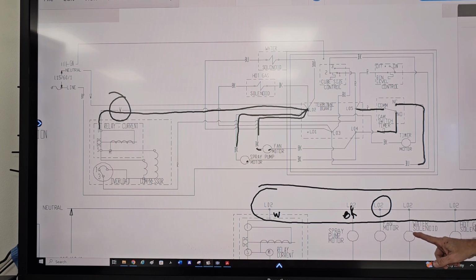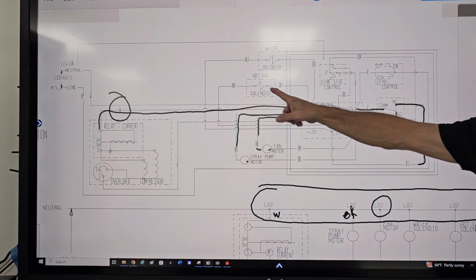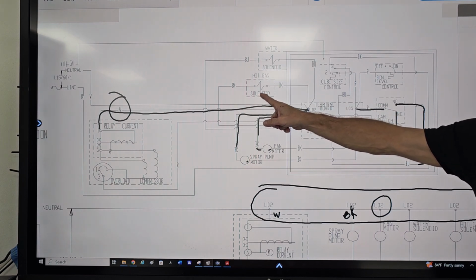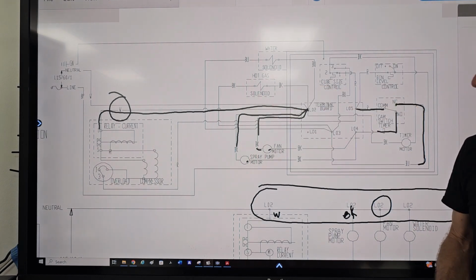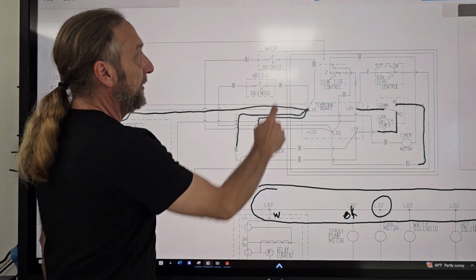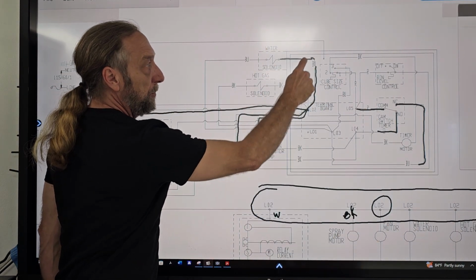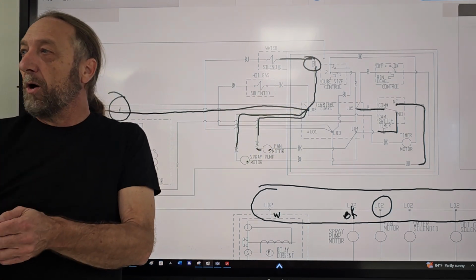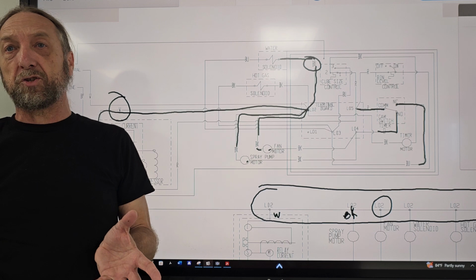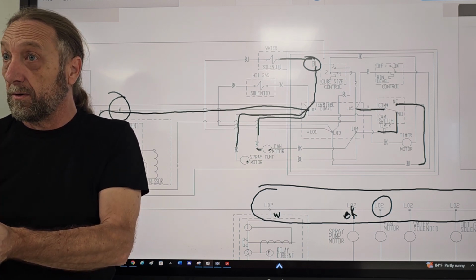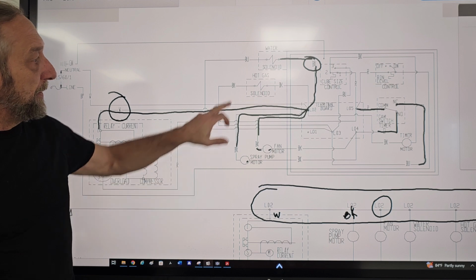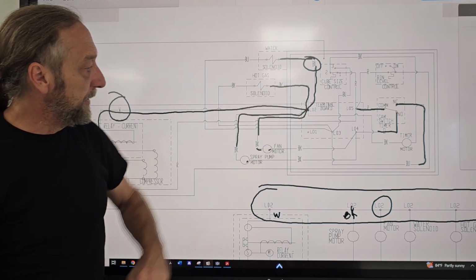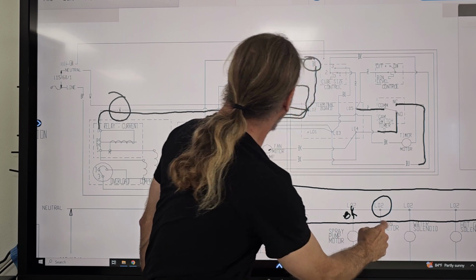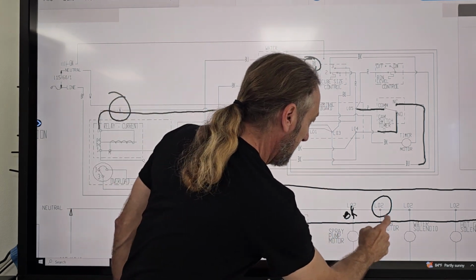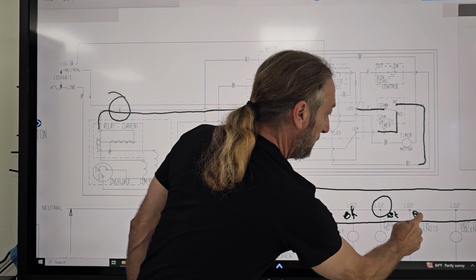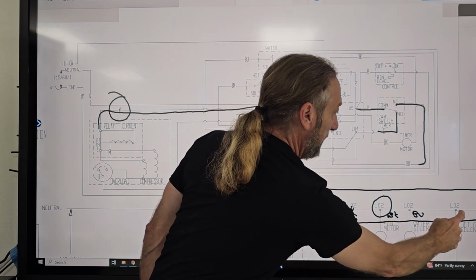Okay, and then the next one is the water solenoid. Where's my water solenoid? This is the water one, this is the hot gas solenoid. One is for water, one is for the refrigerant, and one side of the solenoid goes to L02. What color is that? Blue. So that terminal has blue, white, and black wires all in the same connector, that's just the way it goes. How about the hot gas? It has a black going there. So the fan motor was black, the water solenoid was blue, and the hot gas solenoid was black.